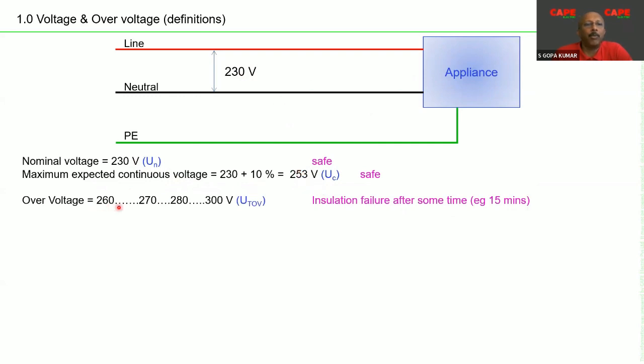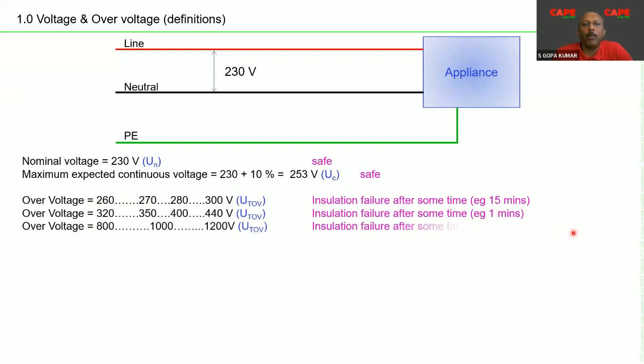253, let's say for example 260, 270, 280, 300, these are actually not the normal voltage, or these are not the maximum continuous operating voltage. These are voltages which can come intermittently, temporarily, due to some problem in the line for certain time, not for a longer time. So under this condition, probably your electronic appliance is able to withstand, let's say, for example, 15 minutes. Higher voltage, 320, 350, 400, 440 volt, again higher voltage. Under this condition, still your equipment probably may withstand a few minutes. Example, 1 minute. Again, up to 1000 volt, 1200 volt, your equipment may withstand up to 10 seconds.